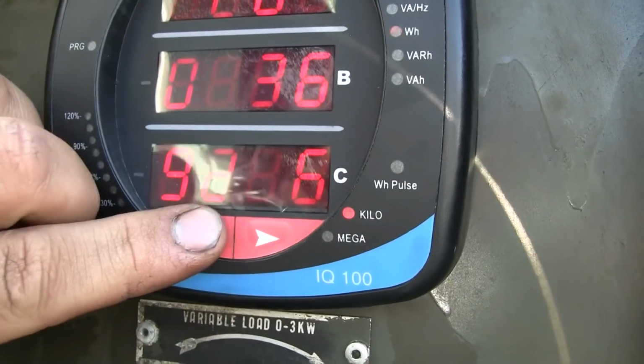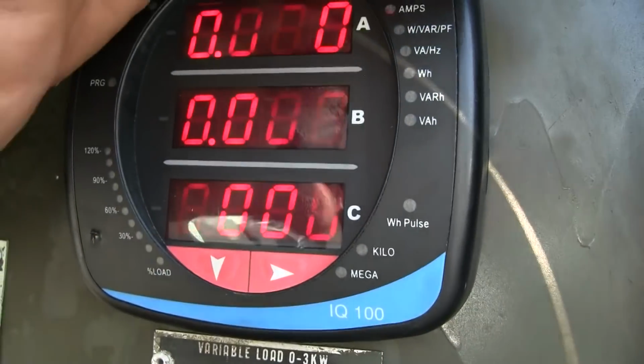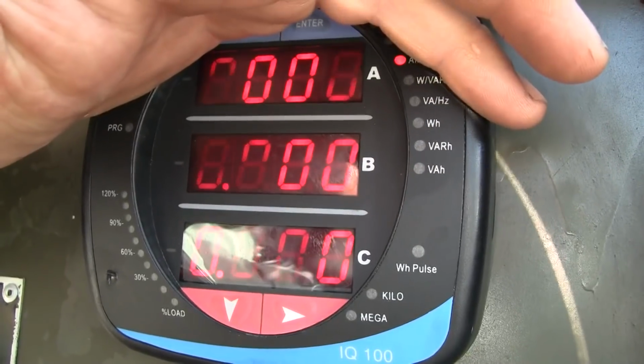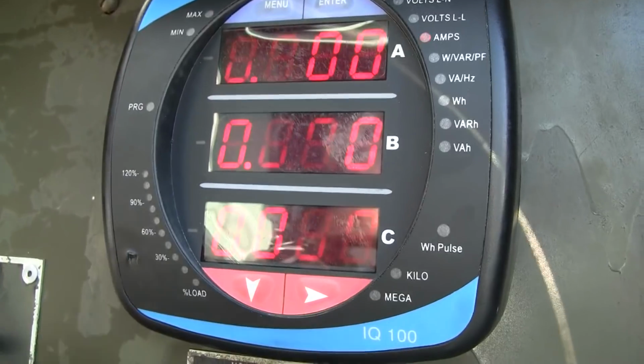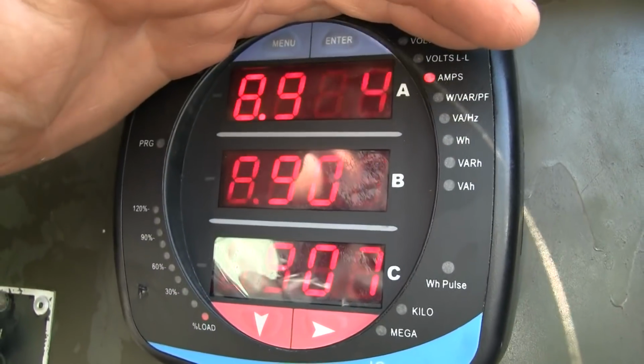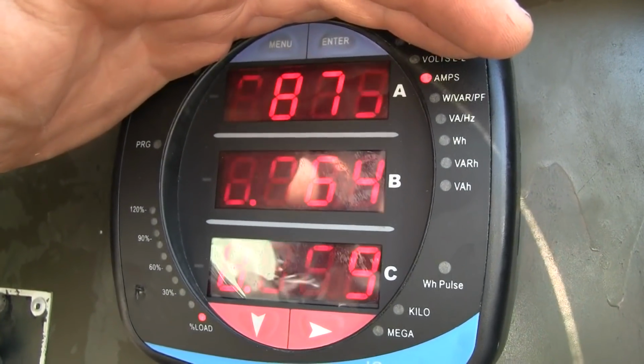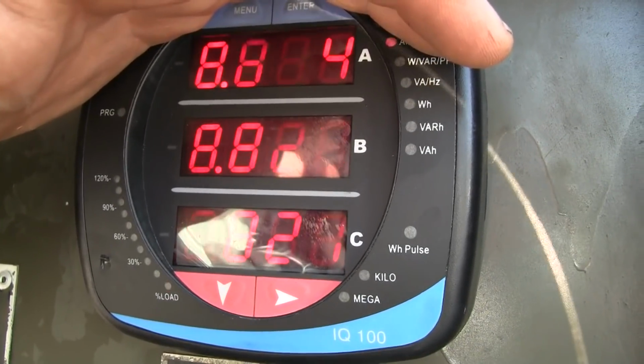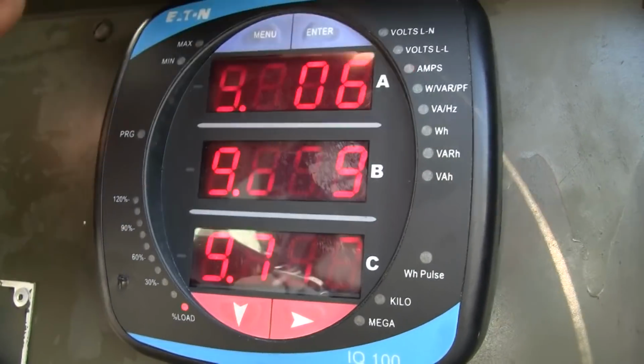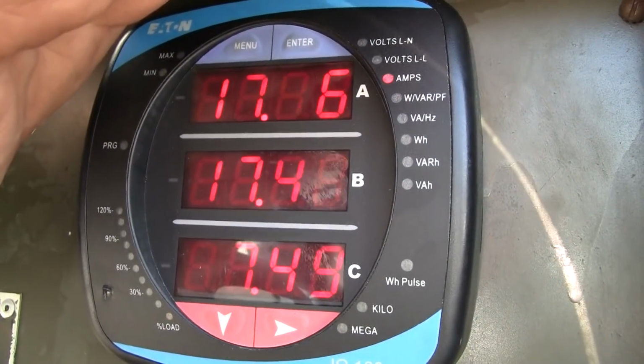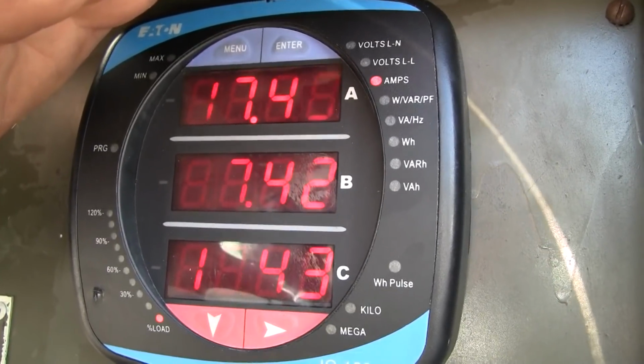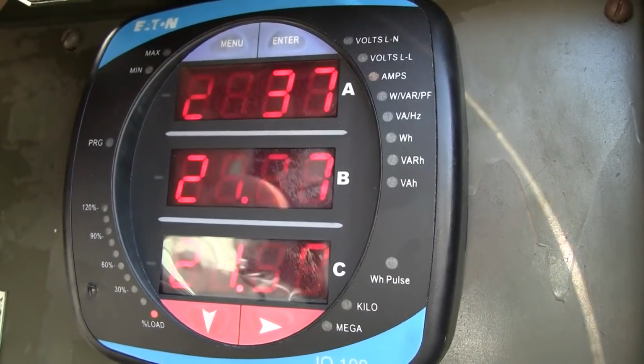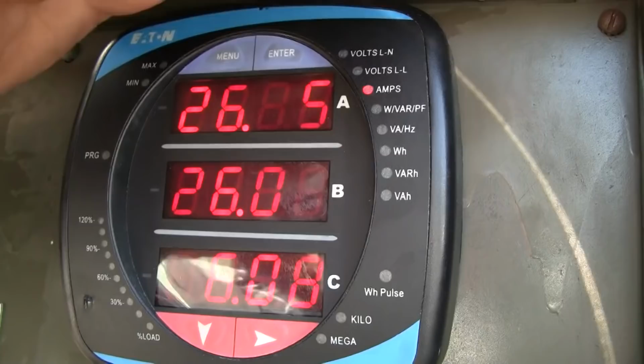Now it's thoroughly warmed up. Let's hit it with some loads. Go back to amps. So 50 amps is full load. Let's start out light. You can't hardly hear the generator run. It's about 8 amps, 8.8. Let's step it up a little bit. 17 amps. And 26 amps. About half load.